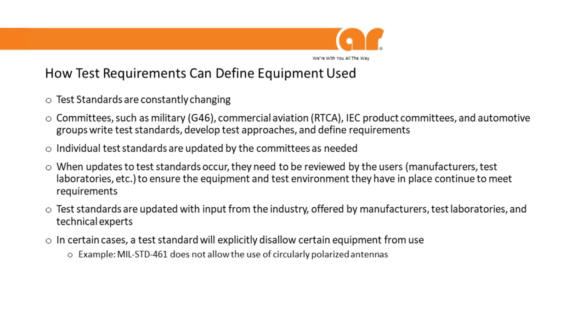Test standards get updated through input from manufacturers, test laboratories, and technical experts. When a committee decides to update something, they request feedback and comments, send out a draft specification, get it reviewed, and then finalize the test standard — usually a lengthy iterative process. In certain cases, committees will remove certain equipment from use. For example, MIL-Standard does not allow the use of circularly polarized antennas.